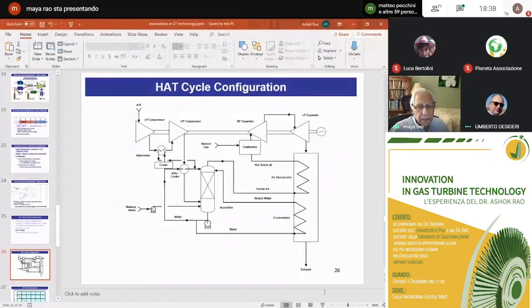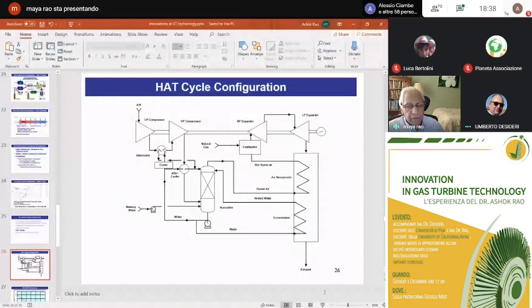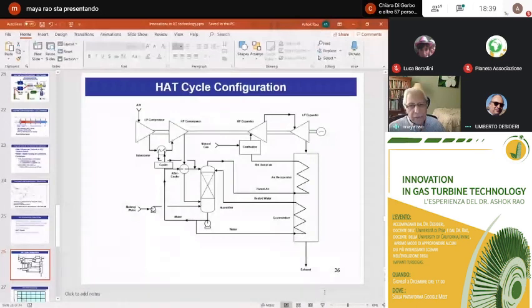It will require some changes, of course. You get a larger volume of gas coming to the combustor, so if you're within the Wobbe index, you're okay. But beyond that, the valve and inlet piping to deliver the fuel may have to be modified, and the exhaust temperature from the gas turbine might be higher because of the hydrogen introduced. The working fluid temperature might increase, and one will have to look at the temperature profile through the expander, and might require some reduction in the firing temperature so you don't go beyond the design temperature of the turbine.